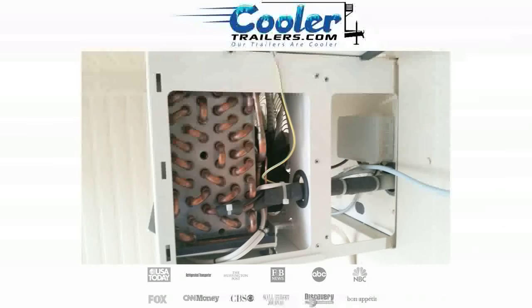The next method is a step up, but it's not the best, and that's electric defrost. The easiest way to describe this is it's like having a toaster oven element on the back side of your coil, and it usually takes 30 to 45 minutes each cycle. It'll only defrost the ice where the heat coil is and doesn't completely remove the ice, so you'll have to defrost more frequently, and running these heat strips is more expensive to operate. Heat strips or electric defrost are less expensive to purchase, but more expensive to operate. That's the important takeaway here.